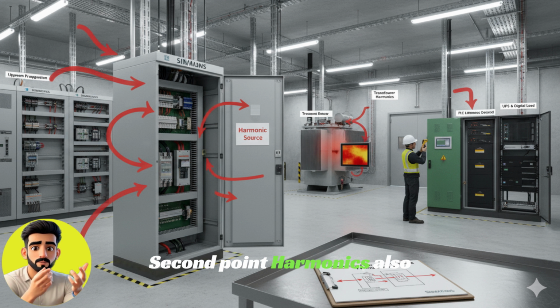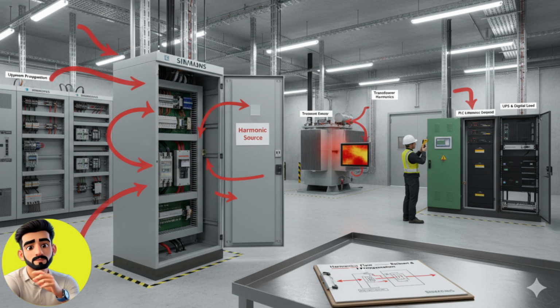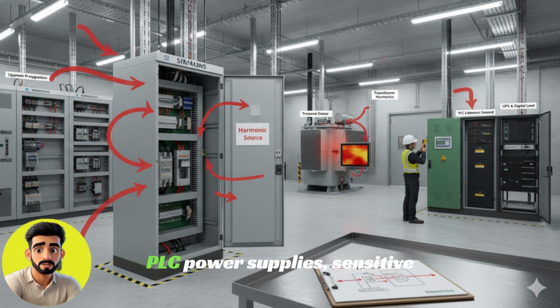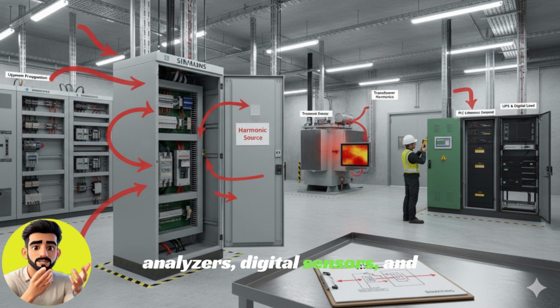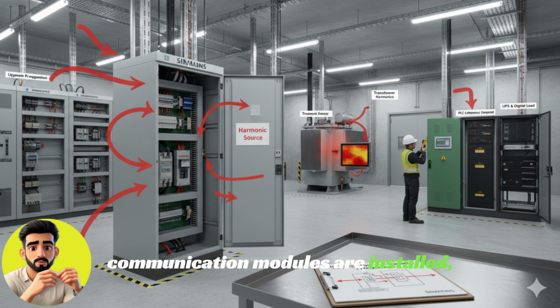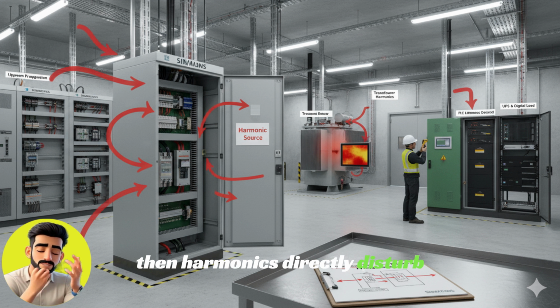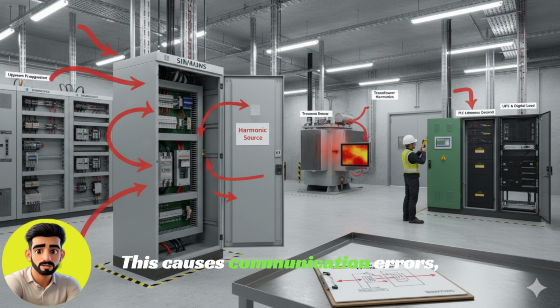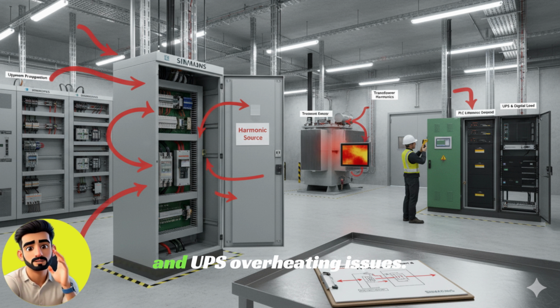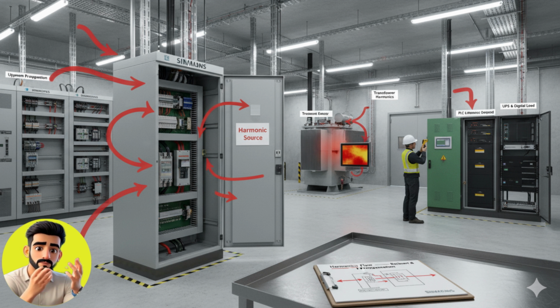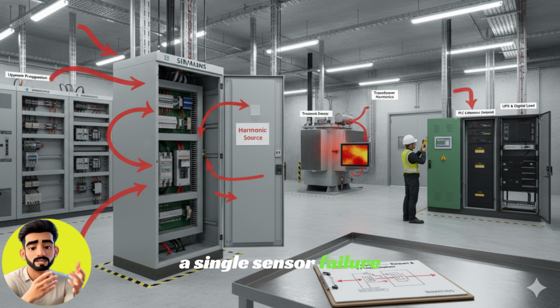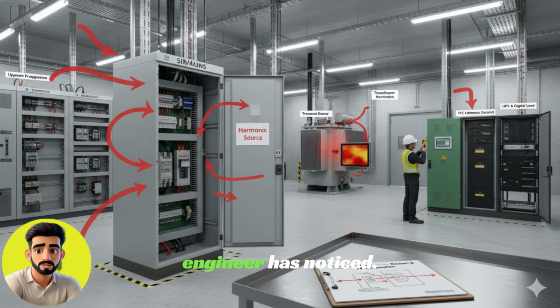Second point. Harmonics also disturb downstream equipment. If the plant has UPS systems, PLC power supplies, sensitive analyzers, digital sensors, and communication modules installed, then harmonics directly disturb them. This causes communication errors, PLC resets, sensor malfunctions, and UPS overheating issues. Often in the plant, a single sensor failure stops the entire process, and the root cause is harmonics, which no engineer has noticed.